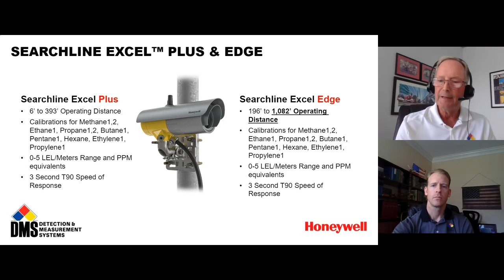So let's talk a little bit about this operating distance and dwell on it a bit more, because this is very important. First of all, with an open path infrared hydrocarbon gas detector, the operating distance that you're going to get out of an open path detector boils down to two things. First of all, the intensity and the quality of the projection of the infrared beam by the infrared source. It has to be a very intense IR beam, yet eye safe, so that it's not dangerous if you happen to look into it. And then what you do with that light at the receiver end to maximize it in terms of the signal and the signal to noise ratio that you get.